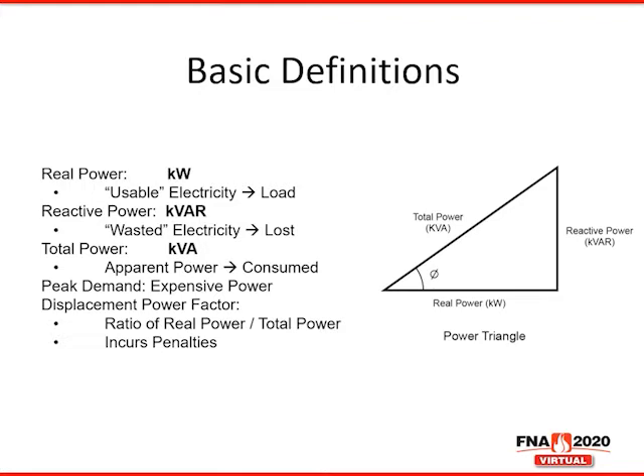Before I get into the results of our case study, I wanted to go over some basic definitions of power. So real power, or kilowatts, is our usable electricity. Reactive power, or kVAR, is our wasted electricity. On the right here, you can see our power triangle, where real power on the bottom is 90 degrees out of phase from our reactive power, or kVAR, on the right. The angle that this forms is known as the displacement power factor. I'll go into this more later, but it's essentially how the current can lead or lag from the applied voltage.